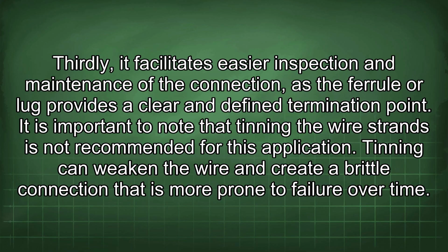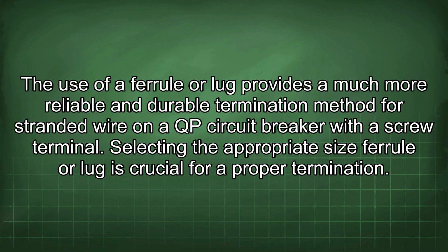defined termination point. It is important to note that tinning the wire strands is not recommended for this application. Tinning can weaken the wire and create a brittle connection that is more prone to failure over time. The use of a ferrule or lug provides a much more reliable and durable termination method for stranded wire on a QP circuit breaker with a screw terminal.